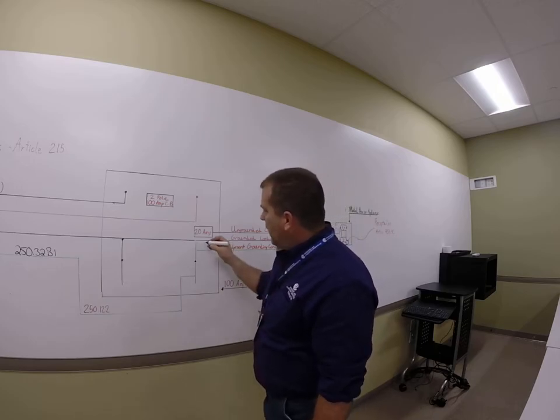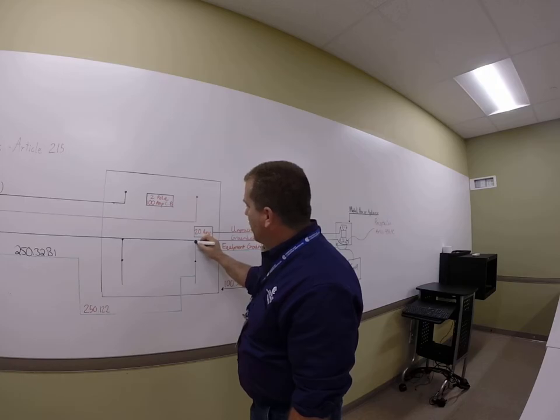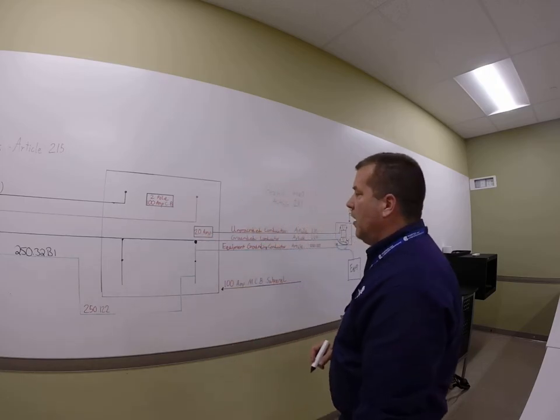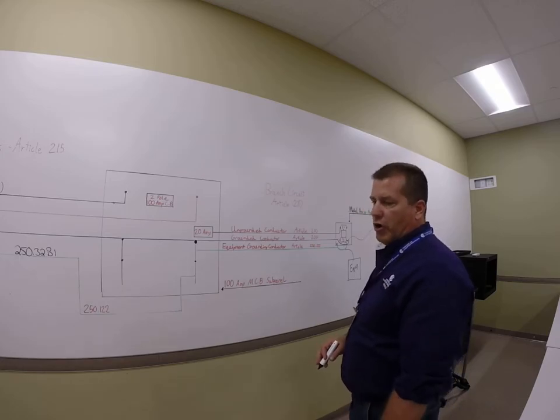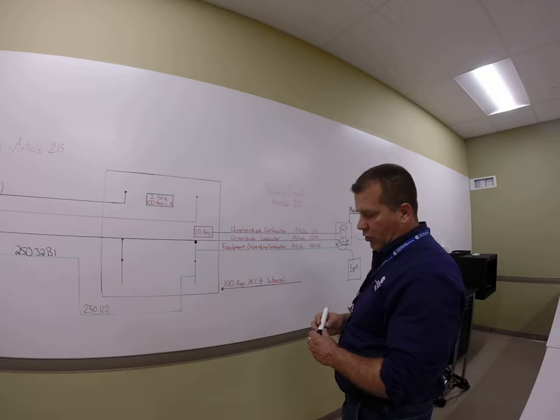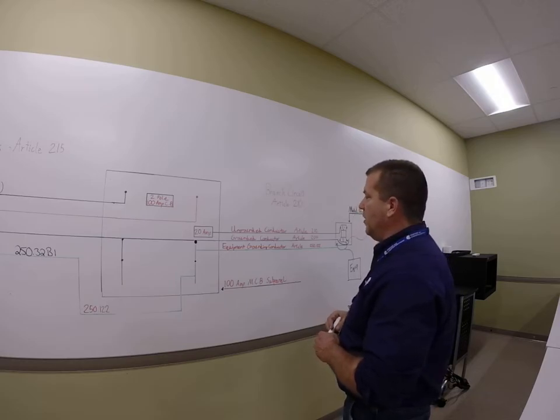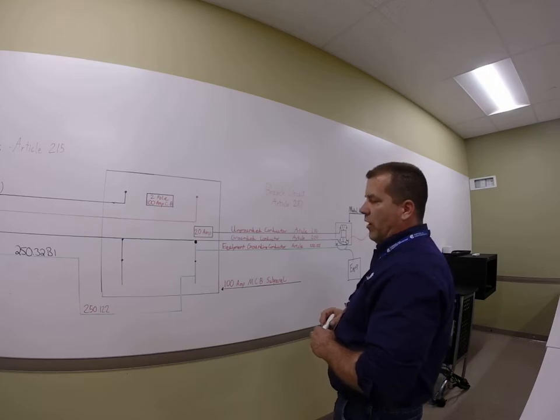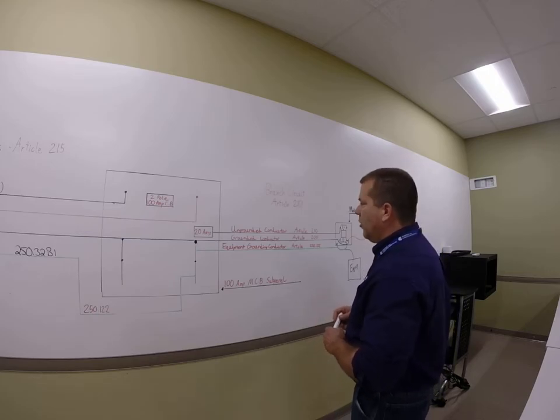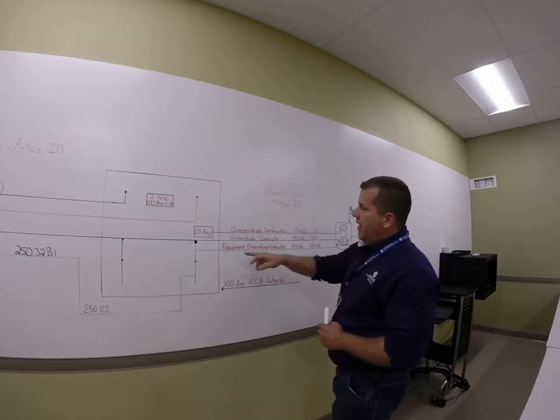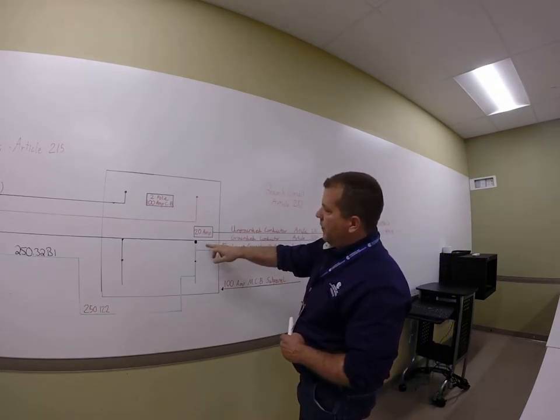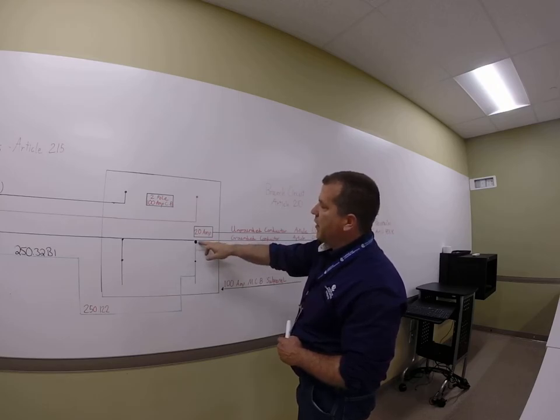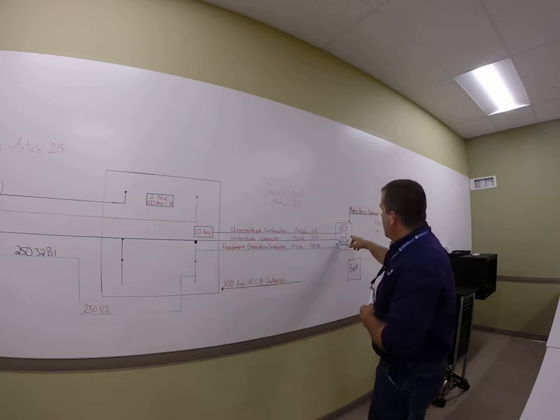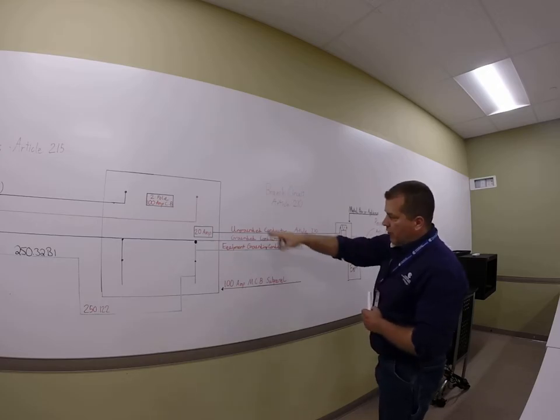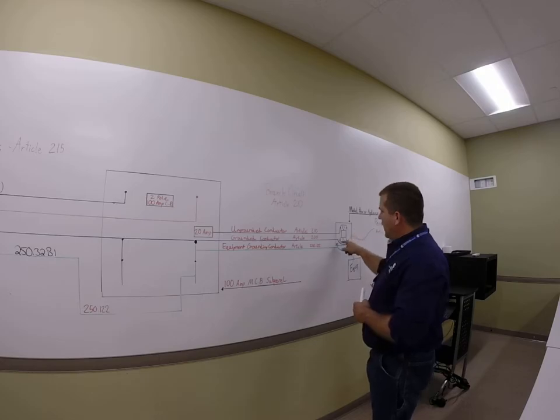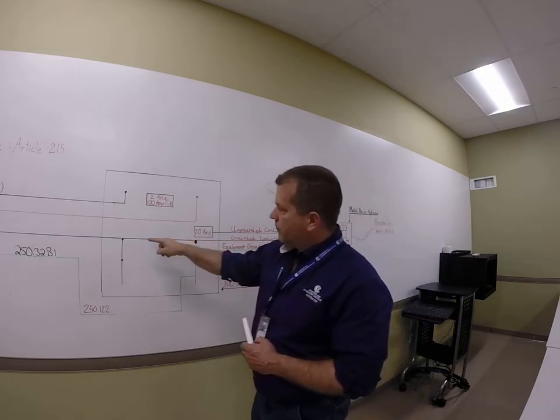But on the other side, let's say I put the main bonding jumper in here. The other mistake that could happen is you can create what's called objectionable current. Objectionable current is found in the code book in Article 100. And what that is, we accidentally will have ground current. And how can we get ground current? Well, if I have the grounded circuit conductor and the equipment grounding conductor bonded at a subpanel, anything that's connected to the neutral of this load or any other loads that are in that panel, well, that neutral wants to go all the way home. Wants to go all the way home.